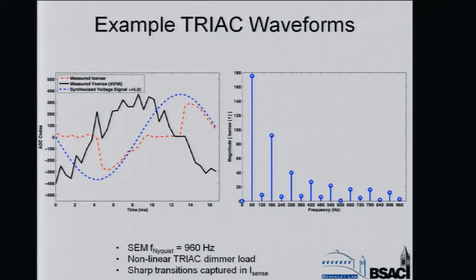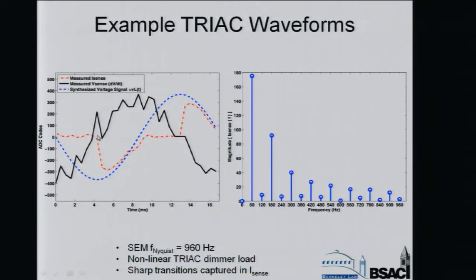Okay, next I'd like to show some waveforms which verify the analog front-end bandwidth of our system. On the left, you can see some waveforms which were taken using a resistive load connected through a TRIAC dimmer. The black curve is the measured Vsense, blue is the synthesized voltage signal, and red is the measured iSense current signal. Looking at the time domain waveforms, when the TRIAC dimmer is in the off state, the current is roughly 0, and when the TRIAC dimmer transitions, there is an abrupt change in the circuit breaker's current. You can see that here as well. Taking the FFT of this data, that plot is shown on the right. You can see that our sensor maintains bandwidth up to the Nyquist frequency of 960 hertz. So this verifies that our sensor is capable of measuring nonlinear loads accurately.